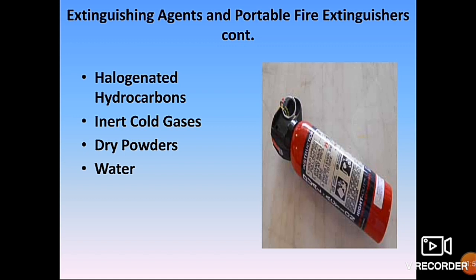All other dry chemical powders have class B, C ratings only, according to US UL fire rating. Dry chemical powder extinguishers control class A, B and C fires, but their use is limited due to residue and cleanup after deployment.